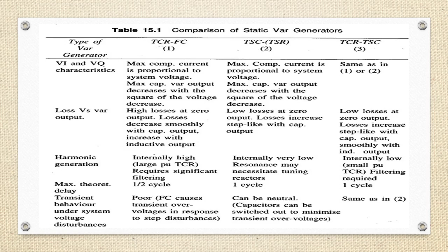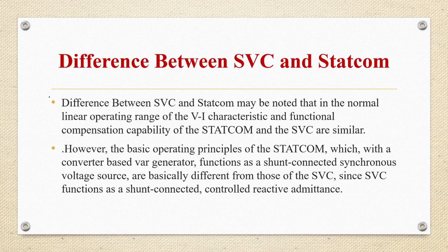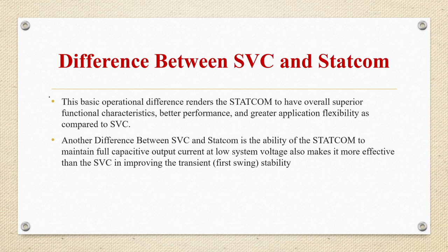The difference between SVC and STATCOM may be noted. In the normal linear operating range of the VI characteristics, the functional compensation capability of the STATCOM and SVC are similar. However, the basic operating principle of the STATCOM, a converter-based VAR generator, is that it functions as a shunt-connected synchronous voltage source, and is basically different from the SVC, which functions as a shunt-connected controlled reactive admittance. This basic operational difference renders the STATCOM overall superior functional characteristics, better performance and greater application flexibility as compared to the SVC. Another difference is the ability of the STATCOM to maintain full capacitive output current at low system voltage, which also makes it more effective than the SVC in improving transient stability.